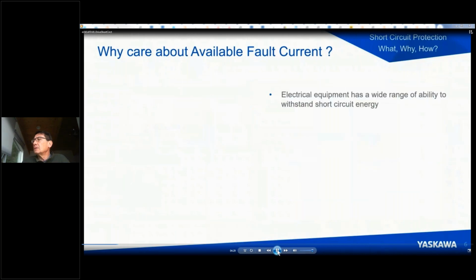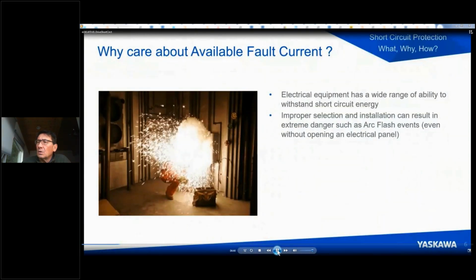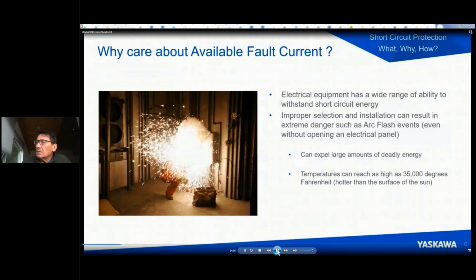So why should you care about it? First of all, electrical equipment has a wide range of ability to withstand that available fault current, or energy resulting from it. Improper selection and installation can result in extreme dangers such as arc flash events, even without opening an electrical panel. It can expel large amounts of energy that's deadly. The temperatures of this energy can be as high as 35,000 degrees, which is even hotter than the surface of the sun. It can throw projectiles, and it can cause normally grounded surfaces to become live.